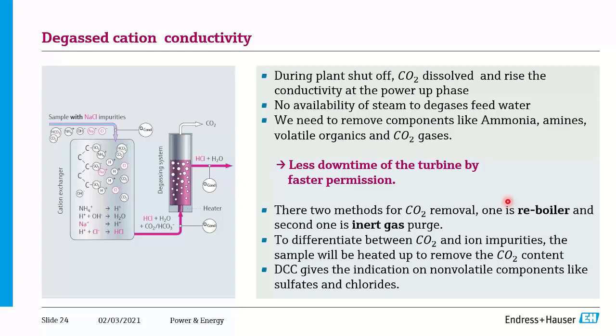Degassed cation conductivity is required when a boiler has been shutdown for a long time and is being restarted, as a lot of CO2 is present. CO2 creates interference in conductivity measurement. When water passes through the cationic resin, ammonium and other species are absorbed, but CO2 cannot be eliminated through the cation exchanger. So CO2 must be removed by the reboiler effect — by heating the sample, CO2 is eliminated, and the resulting sample gives a clear conductivity reading without CO2 interference.